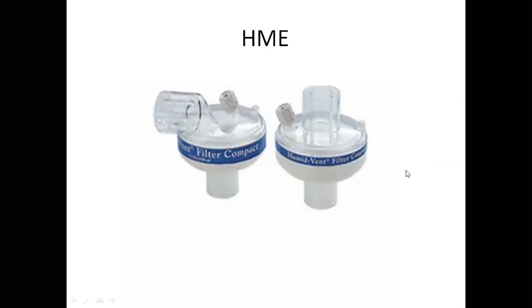And there's some data suggesting now that we just need to keep them on a heated humidified circuit and not even break the circuit 3 days into it to put them on a heated system versus this HME. So that might be the new best practice. We'll see over the next year or so what hospitals start to elect to do if they haven't already. Regardless, this device isn't a heater humidifier, but more of a preventer from letting the patient dry out. Okay, so kind of a quick overview of heating and humidifying oxygen, of providing humidified gas to our patients.